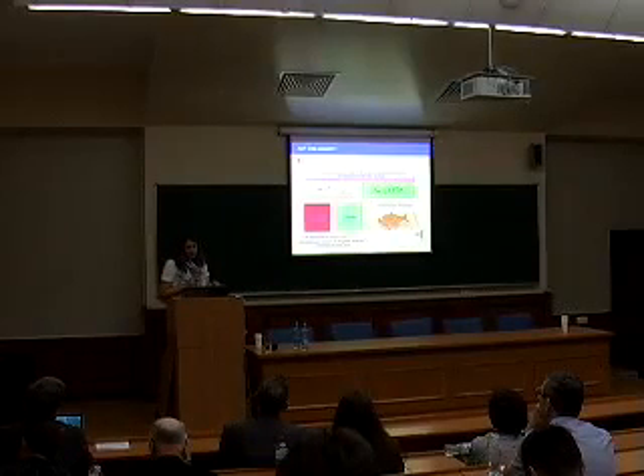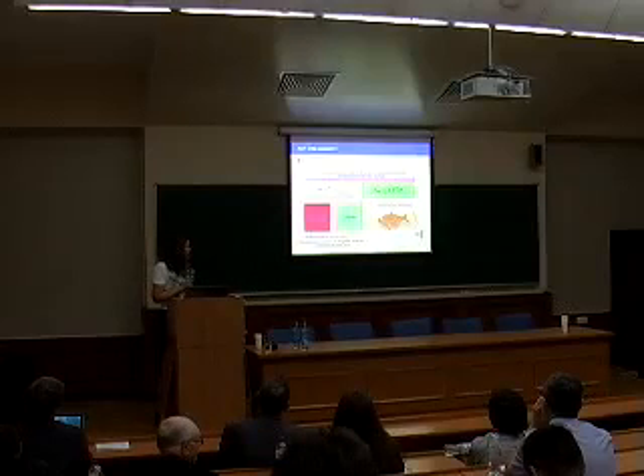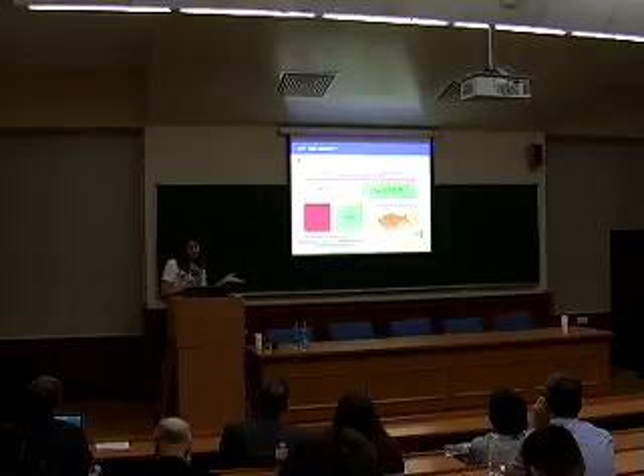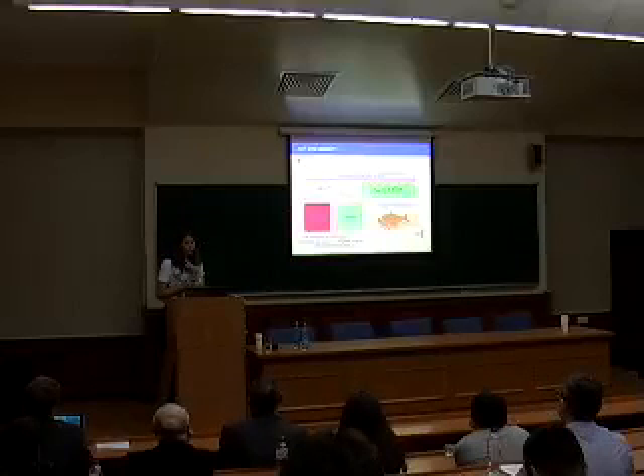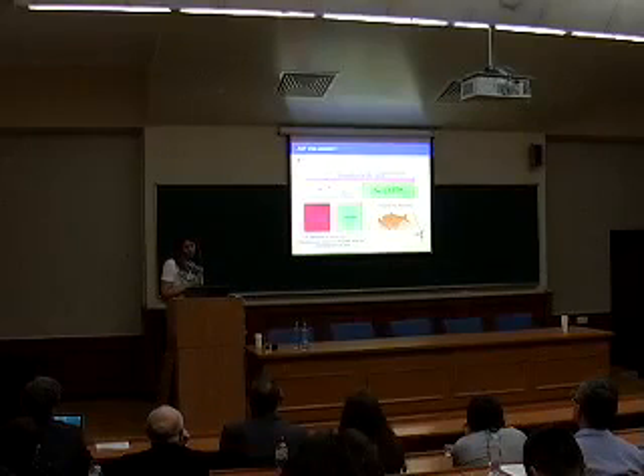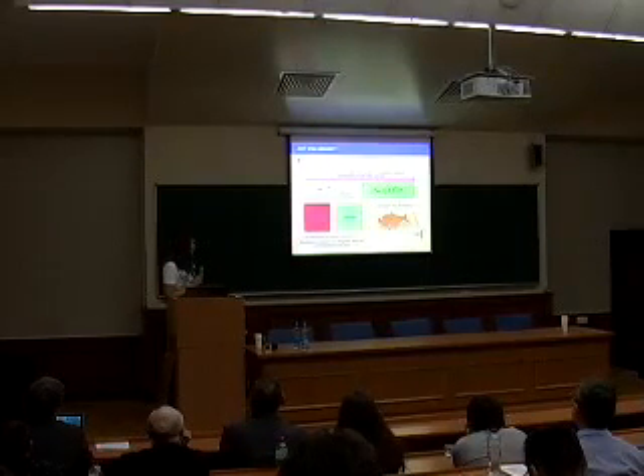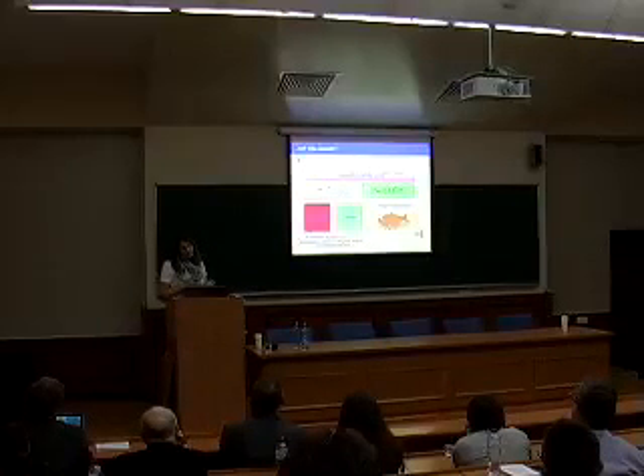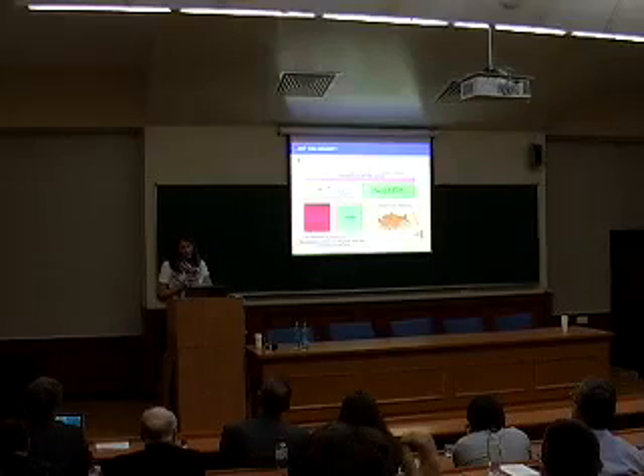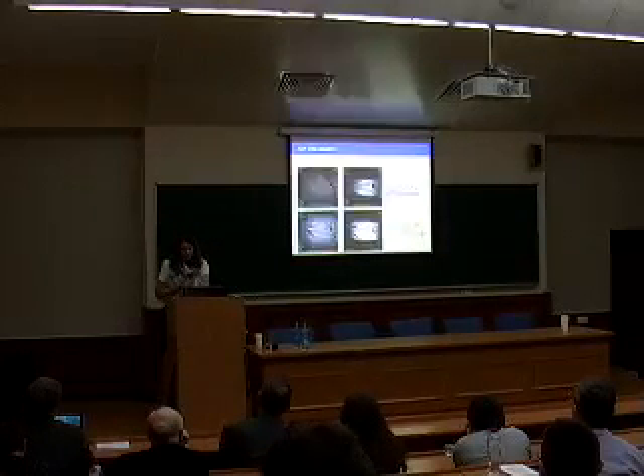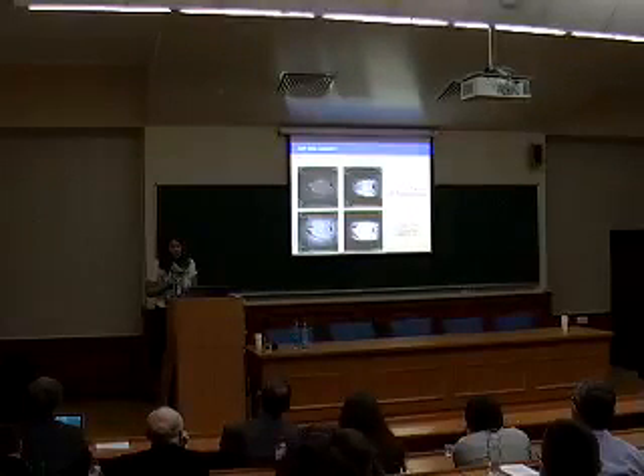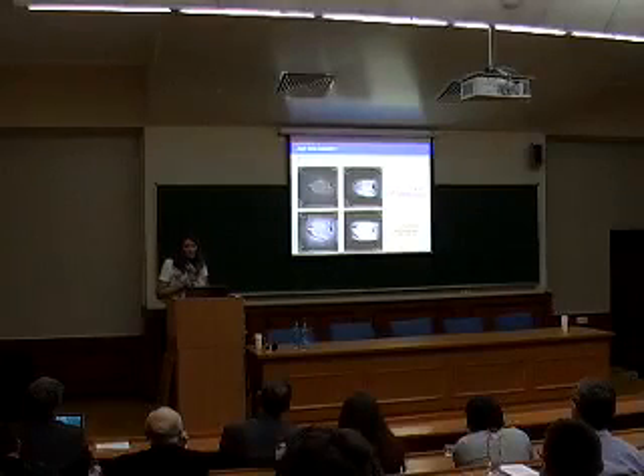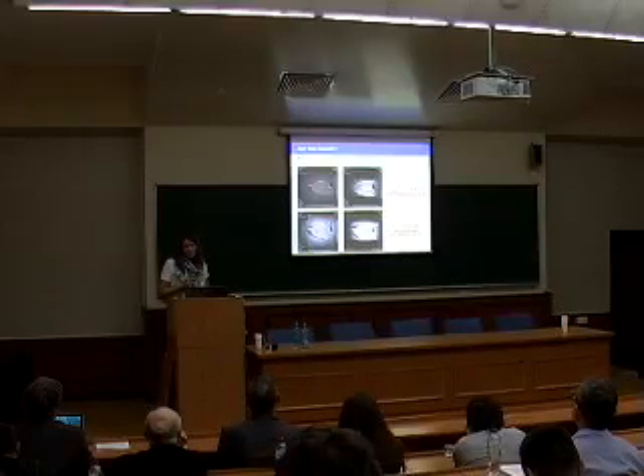First of all, if you look at how SNR is defined in MRI, it's the B1 minus field, don't mind the minus, so it's just the RF magnetic field which the coil is sensitive to, divided by the power which it dissipates in the lossy subject. And as you can see, that power proportionally depends on the electric fields created by the coil. So what does this material actually do? It increases the B1 or magnetic field, H field, while at the same time minimizing the E field by simply redistributing it over the sample, over the fish in the first paper. By doing so, in a standard clinical scanner, here the results shown for 1.5 Tesla, the first result, you could see that SNR could be increased by 2.6 times, just by simply placing that material inside the MRI scanner.